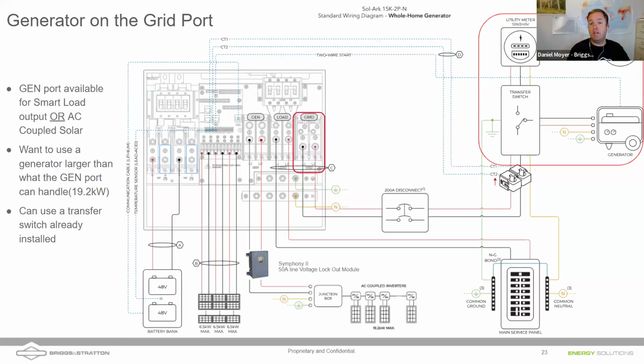Well, two things. We could put in one of our load shedding modules, which can be prioritized so that as soon as it sees the generator start, it opens up and doesn't allow that AC coupled solar to feed into the gen port. Another thing we could do is program the generator to run outside of solar hours. So there are two options there. And what Sol-Ark often recommends, if you have a generator on a transfer switch and AC coupled solar, which is a fairly common situation, is to program the generator to run only during hours when you're not expecting AC coupled solar.